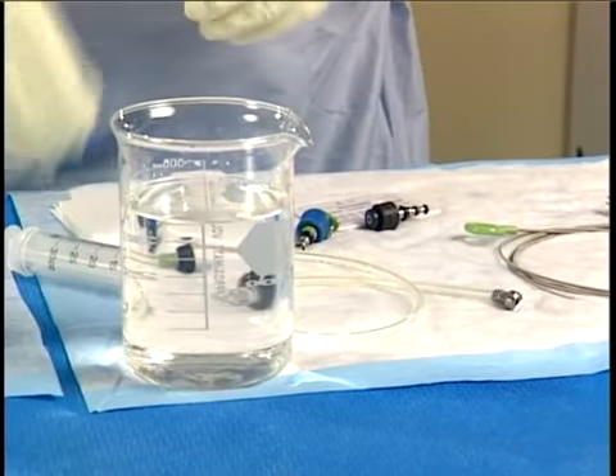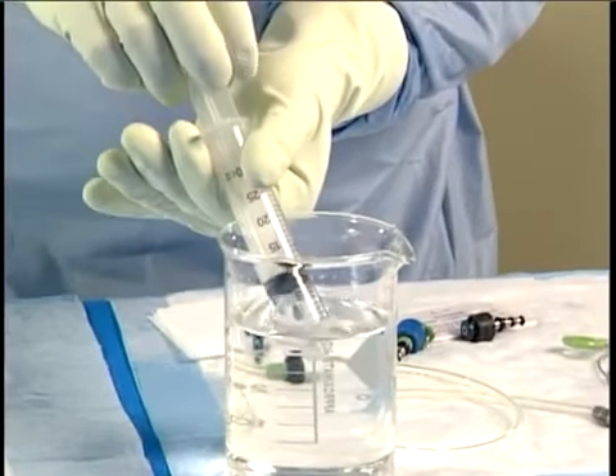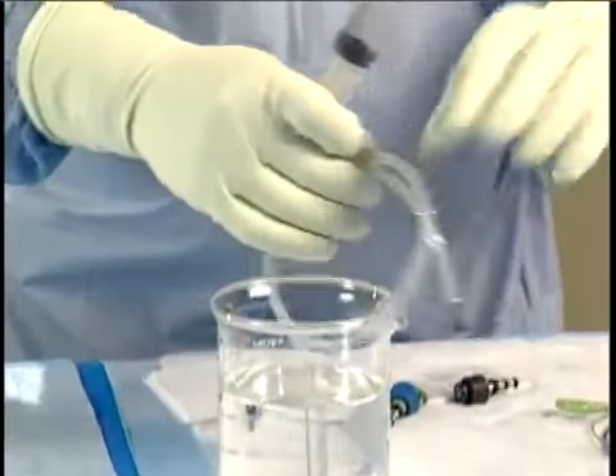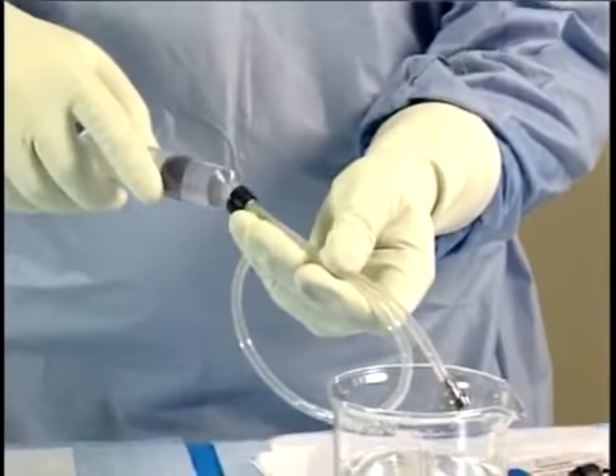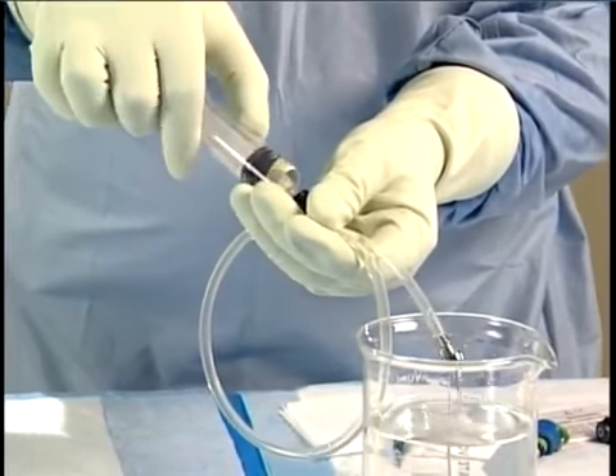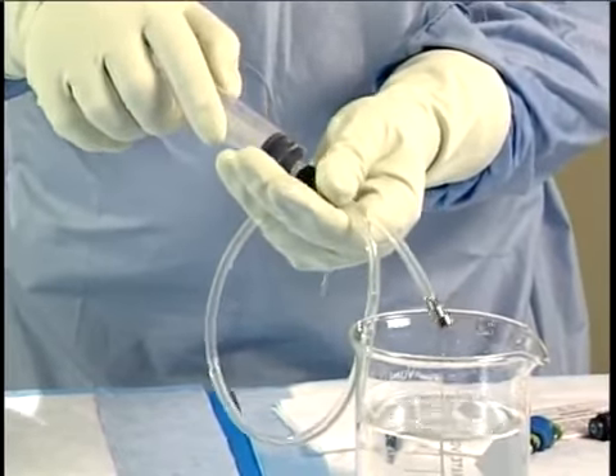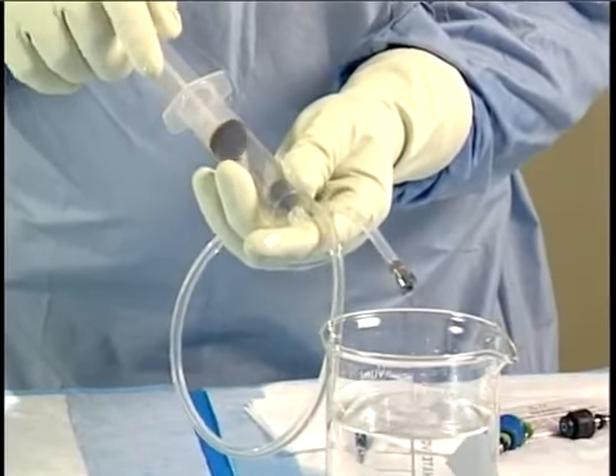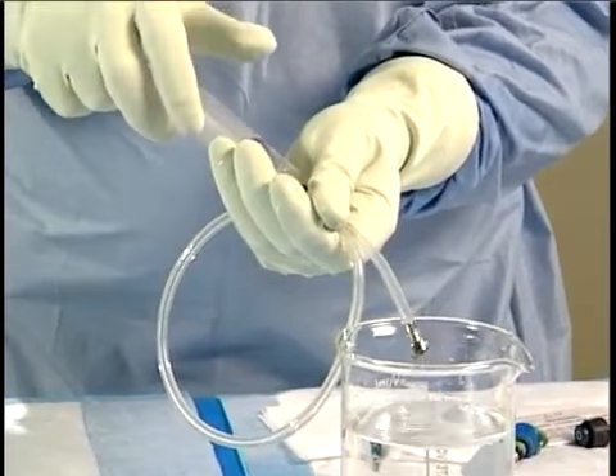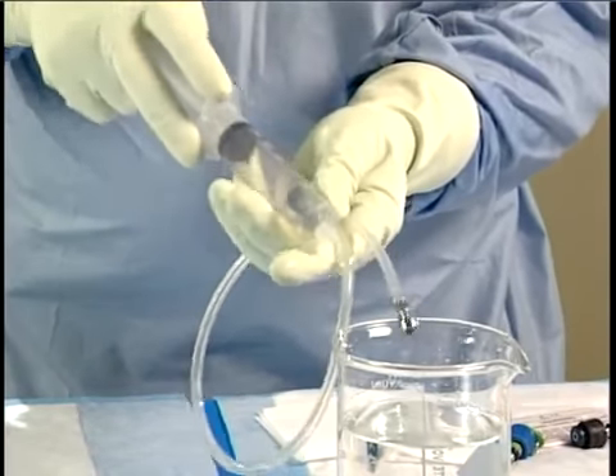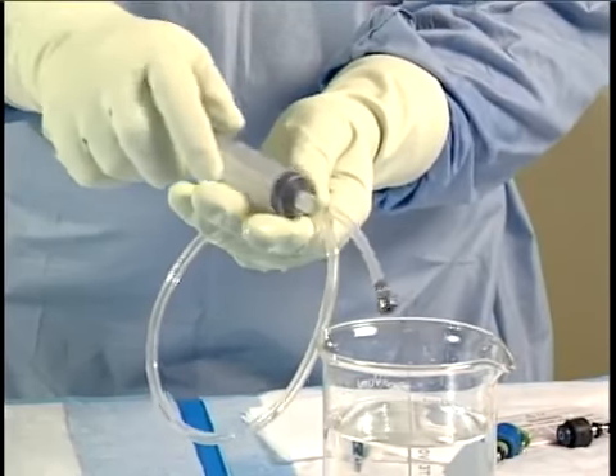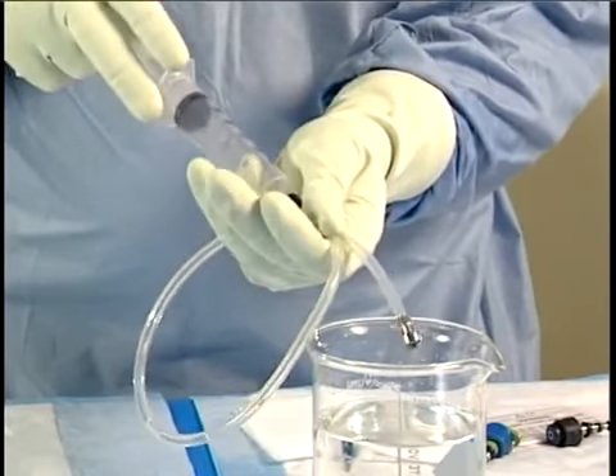If non-sterile water is used for rinsing, the parts must be wiped and given a final flush with 70% ethyl or 70% isopropyl alcohol. Prepare a container with the alcohol. Fill the syringe with alcohol. Attach the syringe to the suction cleaning adapter and flush. Use the syringe to flush air through the suction cleaning adapter to expel all alcohol from inside the tube. Flush with air 3 more times. Place the adapter on a dry, clean cloth.